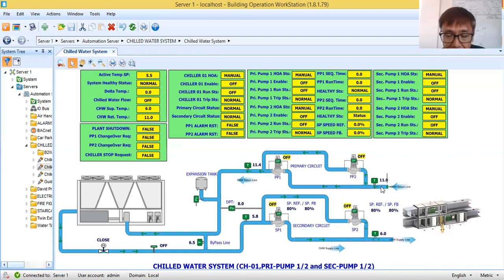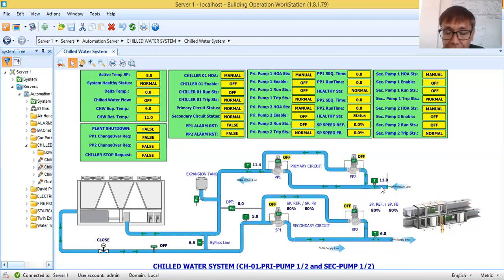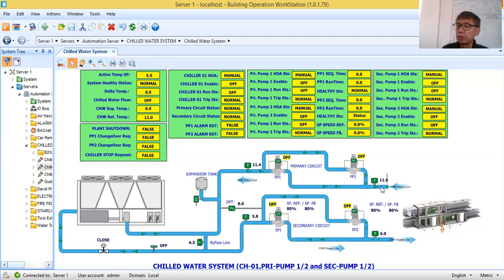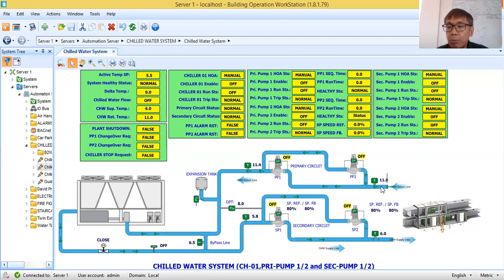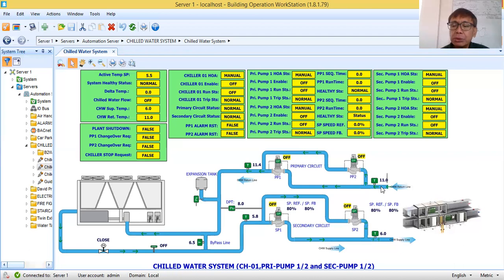As a good engineering practice, we need to ensure there will be equal wear on the equipment. So we will be sequencing the primary pumps and secondary pumps. We will write a control logic program so that, let's say, when primary pump one has been running for one week, it will stop, and at the same time primary pump two will take over. It will change over every week.